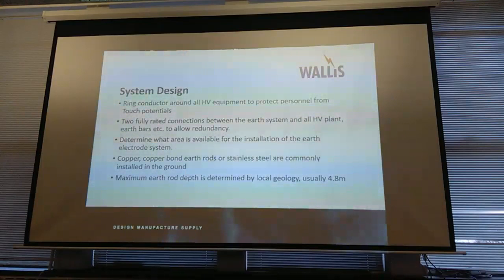Determine what area is available for the earth electrode system. This is becoming more and more of a problem for us as designers, because in a big built-up city like Birmingham, you will want to put a new substation in somewhere, and you'll say, right, you've got that room there. Yeah, but that room's on the 3rd floor. Where am I going to put my earth? Oh, well, there's a little bit of ground out there, and you go out and it's like 2 meters by 2 meters, and you think, yeah, great, thanks for that. There are ways and means to it, but you need to know up front.